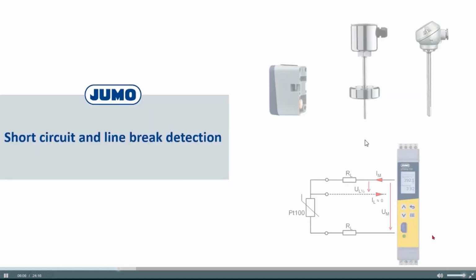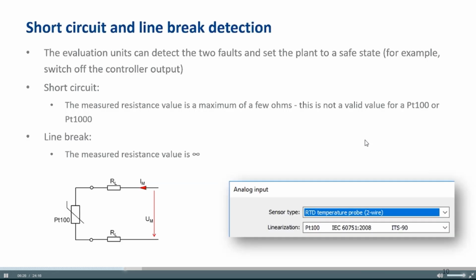So what about short circuit and line break detection? Imagine you have an RTD temperature probe, and in this RTD temperature probe or in the cable, you have a short circuit or a broken line. Here one point is important: if you work with RTDs, both cases can be detected by the evaluation unit.